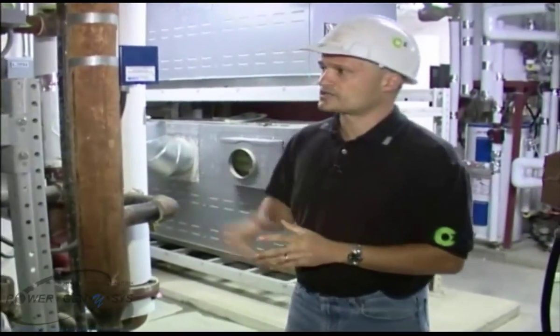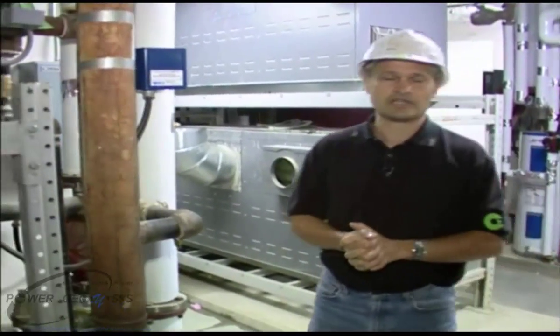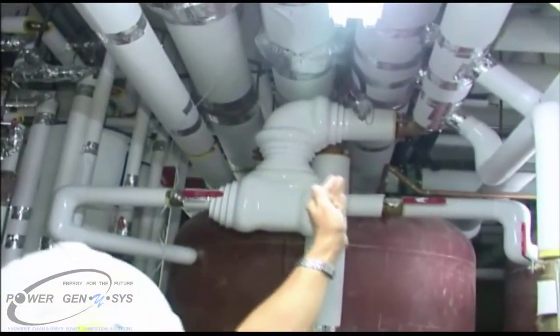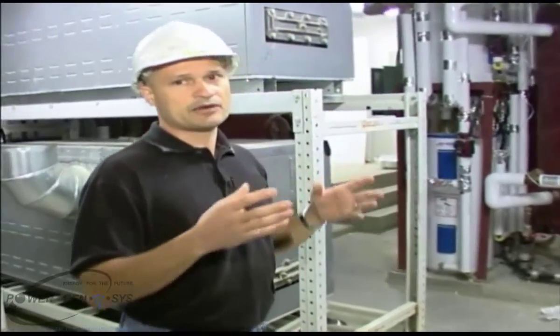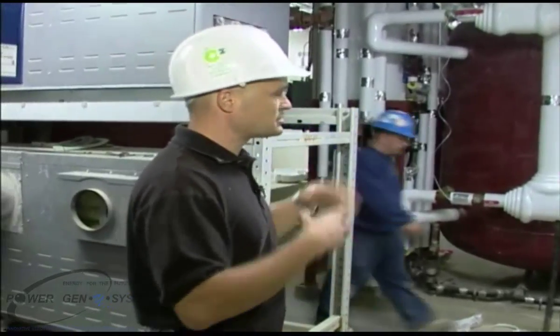Included in the building's heating system are six natural gas boilers, which provide all of the heat for heating the building. Our co-gen system puts all of its high temperature heat into that same loop, and these boilers then add any additional heat required beyond what the co-gen is providing. Our main tie-in point is on the main return line to the boilers — that's where we extract the stream of water we send to our genset. The genset is kept cool, and all of the thermal energy from the engine is put right back into the boiler heating loop, thereby increasing the temperature of the return water. The boiler control system is simple: if extra heat is added, the boilers come down; if more heat is required, more boilers pick up the additional heat requirements.